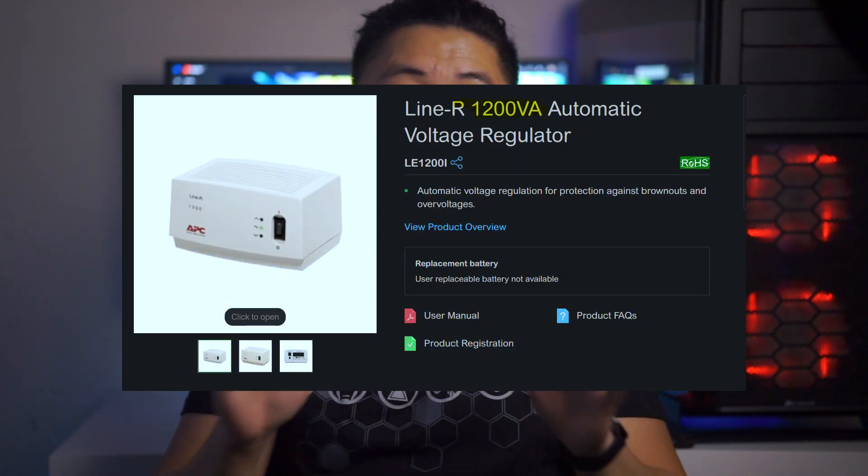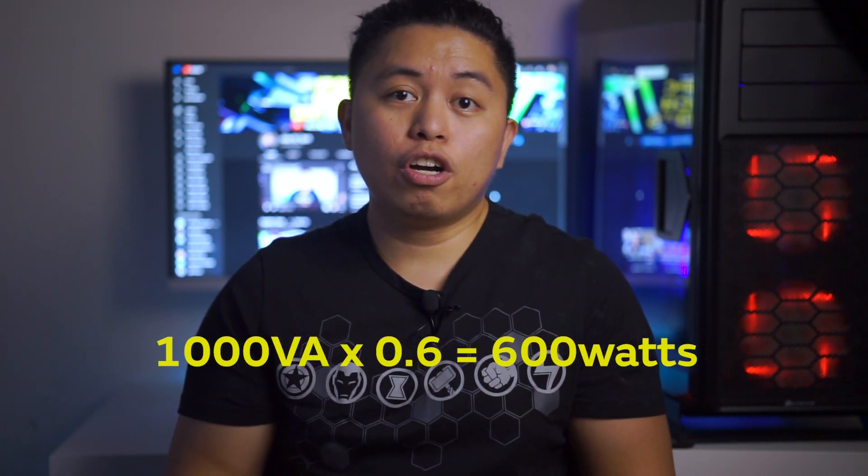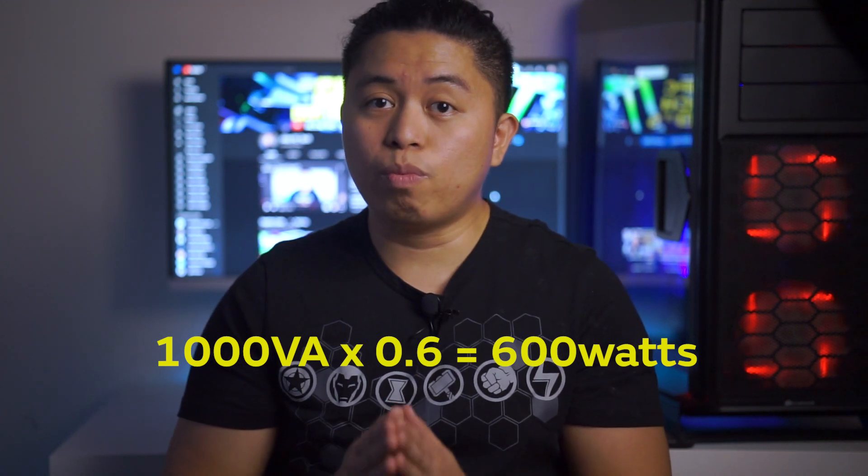When buying an AVR, there is a VA rating that specifies how many watts your AVR can handle at its best. For example, if you buy a 1000 VA rated AVR and multiply 1000 by 0.6, the max capacity of your AVR will be 600 watts — that is the maximum power draw of the devices you connect to it.